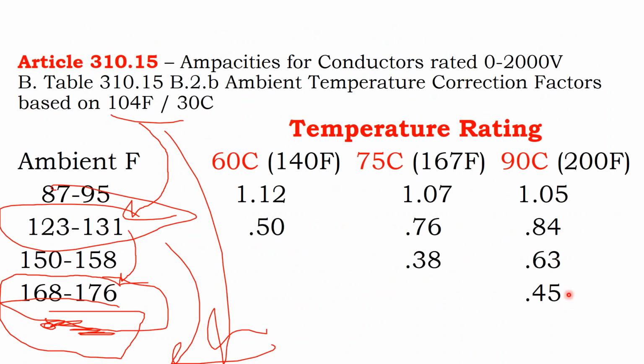So all of a sudden, a cable that's rated for 70 amps, because there's more than 3 in the raceway, gets knocked down to 35 amps. And then because of ambient rooftop temperatures, it gets knocked down another 45%. So now we go down to about 15 amps. And then we have to adjust by the 25% for the continuous load. That goes from 15 amps down to about 12 amps.